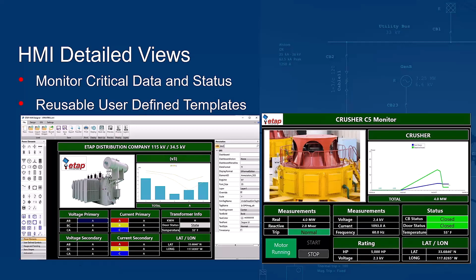Alarms and notifications appear in case an event is detected, or measurements operate outside of a normal range. Custom reports can also provide additional operational data. For example, you can use reports to evaluate energy usage per operating process in an electrical system to evaluate efficiency. Similarly, trends can be used to view changes over time of critical measurements, for example, changes in the power factor over the main lines to evaluate operation efficiency.